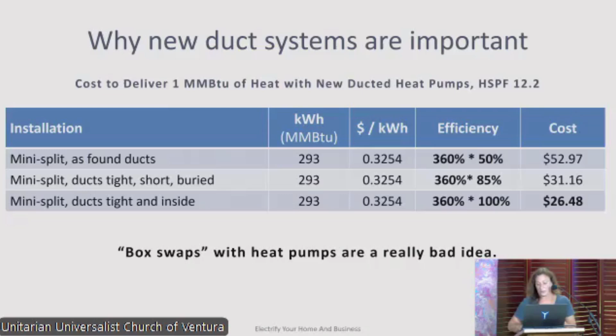When we get the ducts into the conditioned space, that's where the magic really happens. Now we don't have duct losses. We still need the ducts designed for the capacity of the system and kept tight, but getting them inside the envelope eliminates those losses, and you actually get the full capacity of the system delivered to your house for comfort.